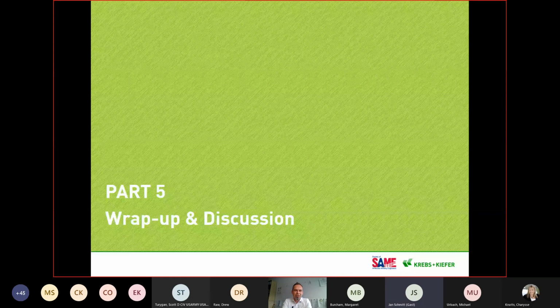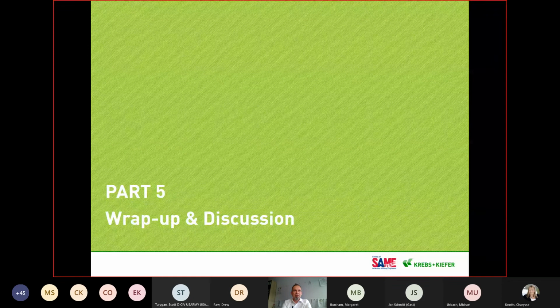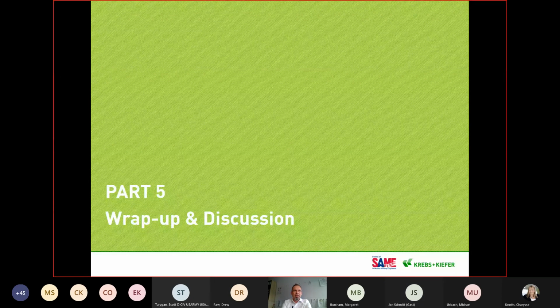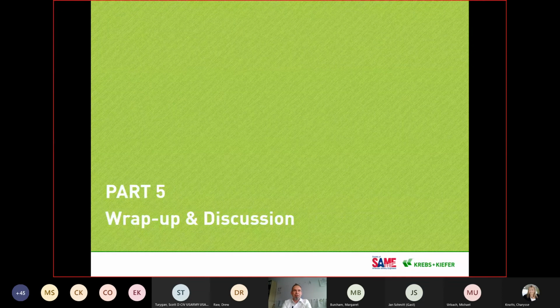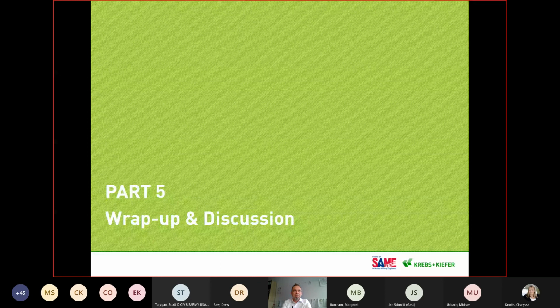First, Jan, I fully agree, and very nice to hear - haven't heard from you in a couple of years. It's always a problem if you have a VDS sprinkler system, for example, built in a US facility, because the purely VDS sprinkler system doesn't meet the NFPA 13 requirements. So in the end, you end up having a mixed system, with parts of the NFPA 13 design in it and parts of the VDS design in it. And that ends up with a maintenance nightmare in my experience.